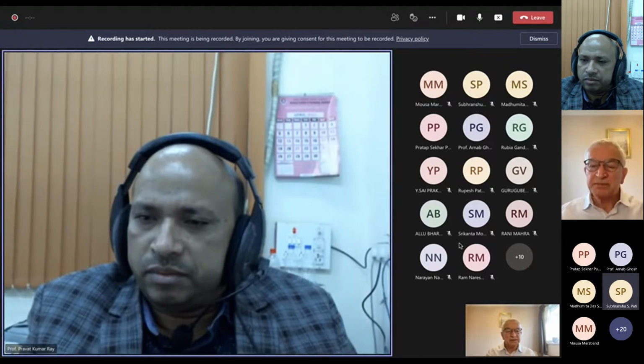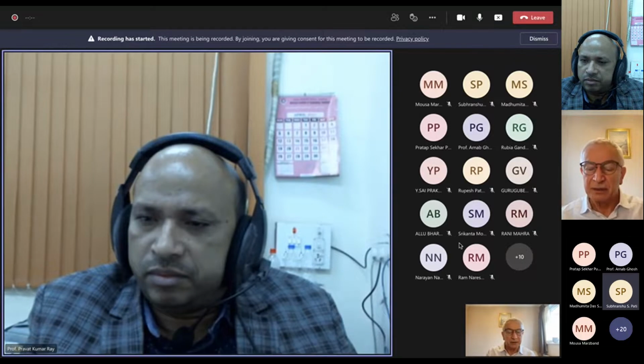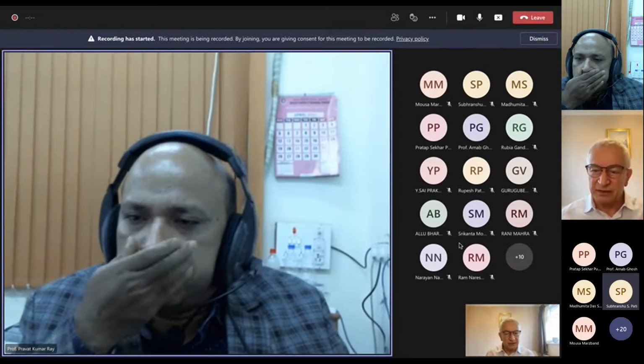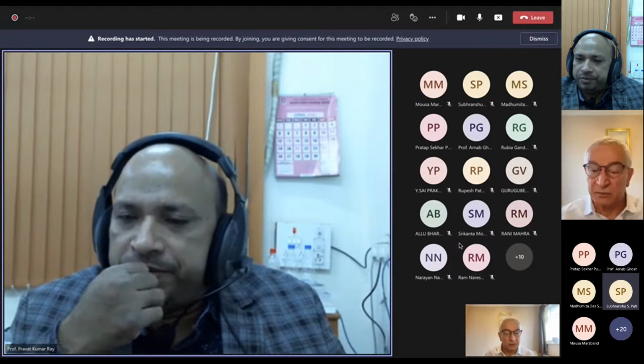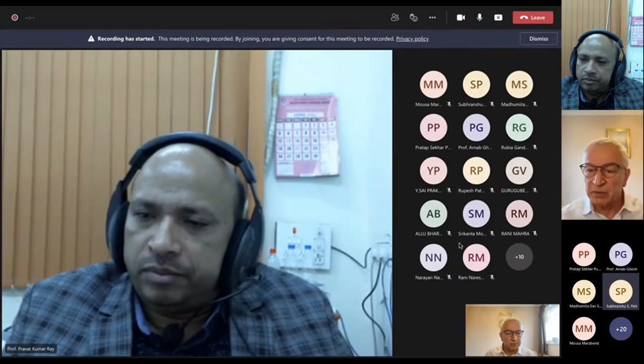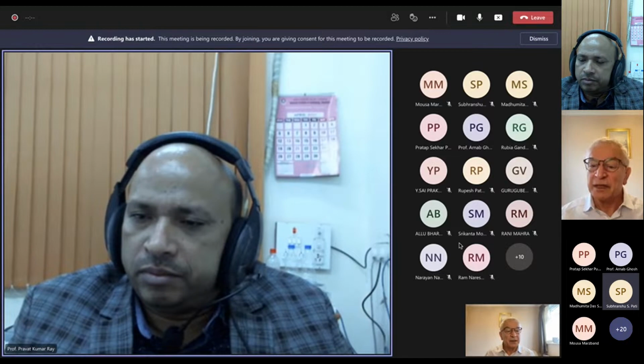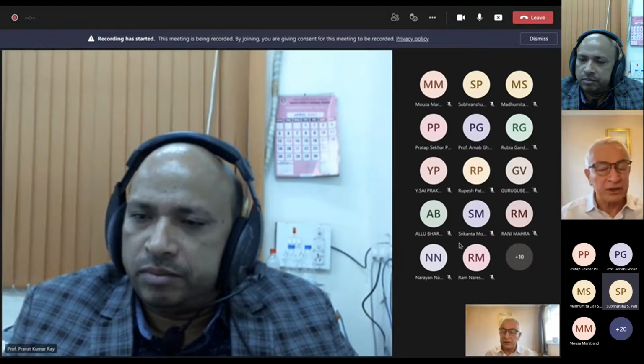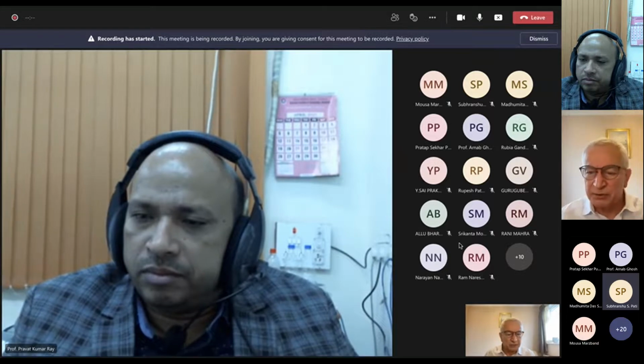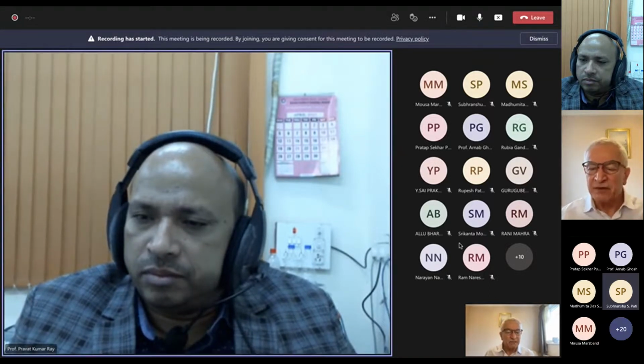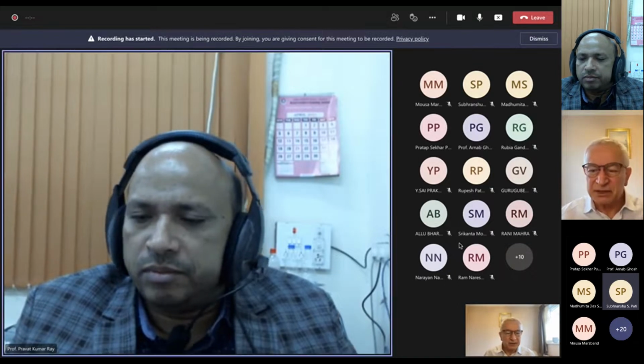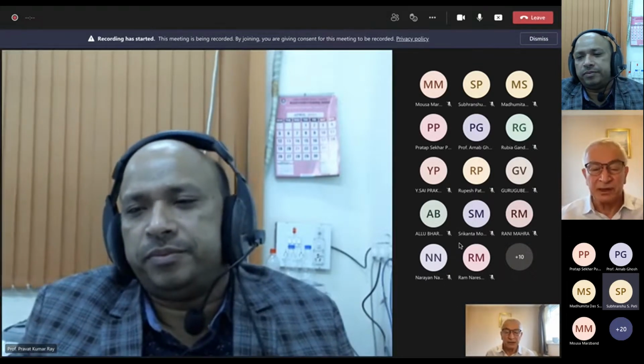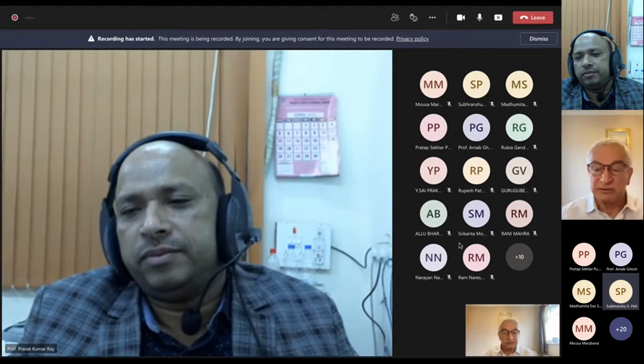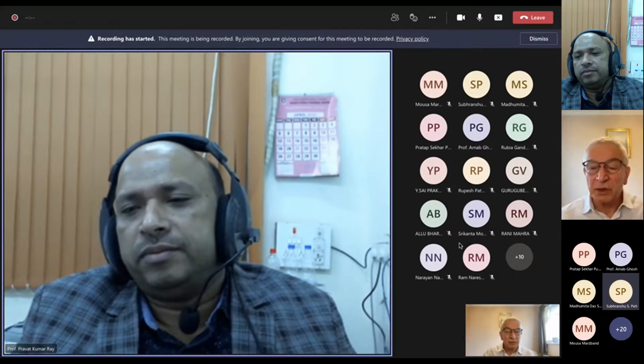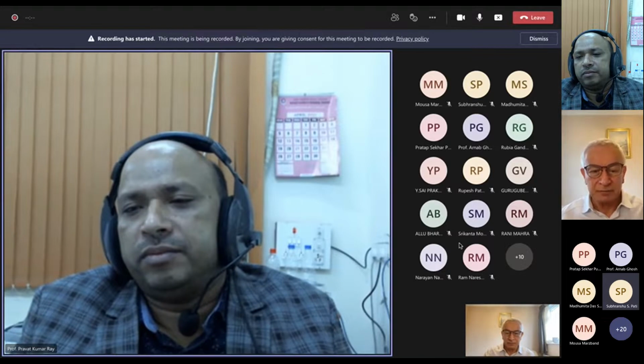So I think once this balance tilts towards electric vehicles, more people will have electric vehicles, more people will have chargers at home, more chargers on the street to meet the demand, and this will increase the demand on the grid. The grid will not be able to cope, as I mentioned in the slides, depending on if it is dumb charging. If you have a localized 10% even of the vehicles changed to electric in a localized area, this can cause a problem to the grid. You can solve the problem by using smart charge control.